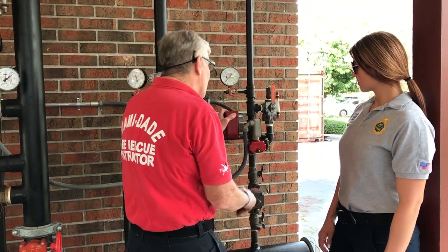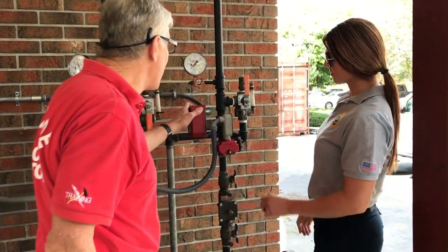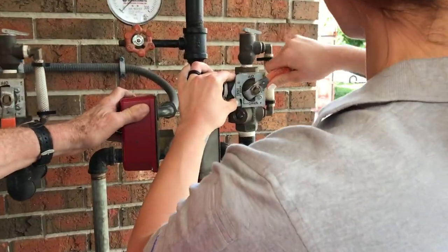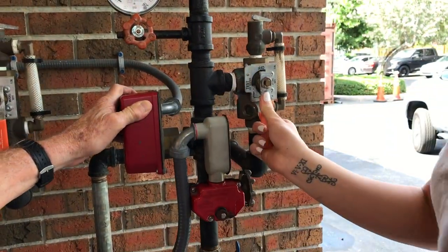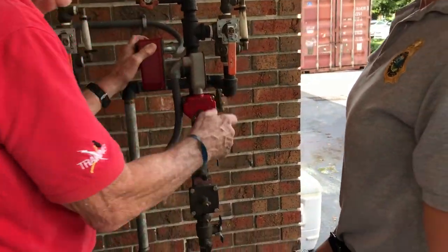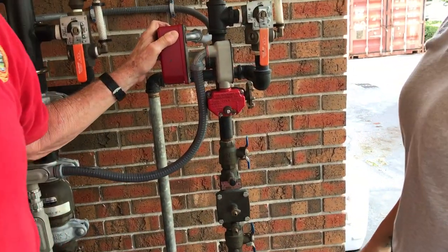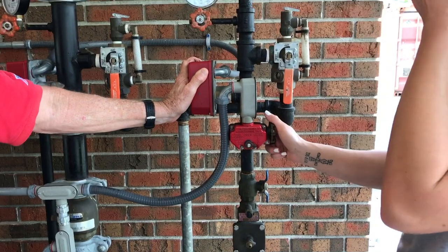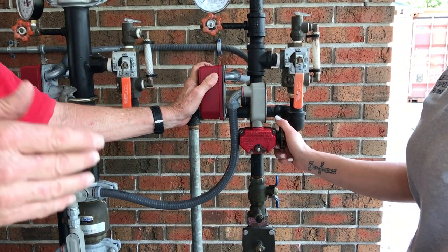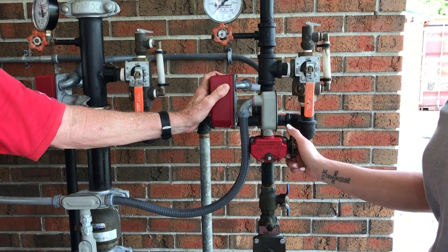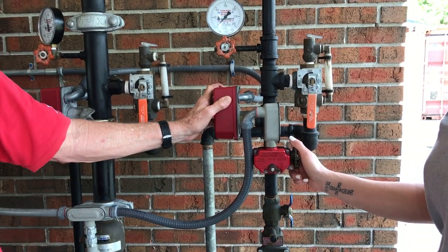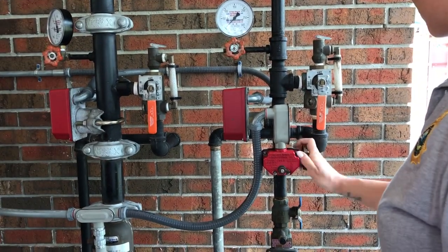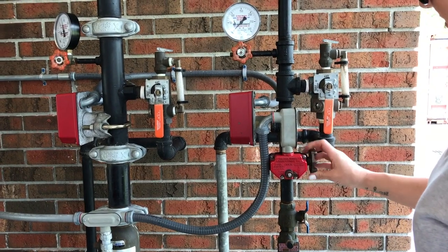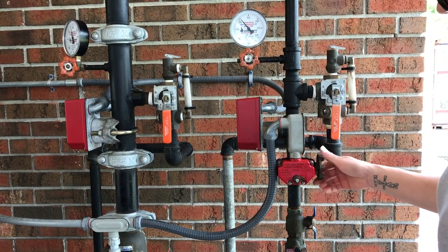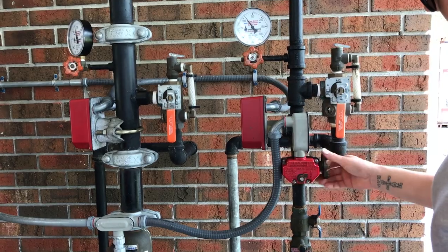Okay, we've changed the sprinkler head, Tammy. We'll go ahead and we'll close the drain. All right. And then we will open the control valve. Now, you may or may not hear this. There's a diesel fire pump and there's a jockey pump. Because we're gonna drop the pressure in the system, you should hear the jockey pump kick on. So go ahead, Tammy, turn it back on. That was the jockey pump kicking back on.